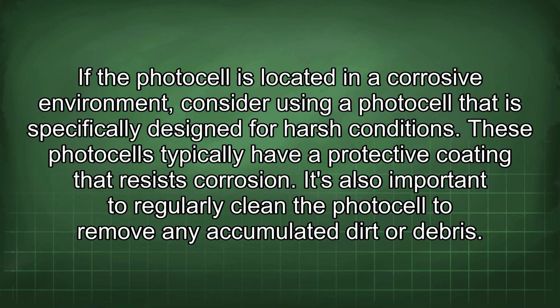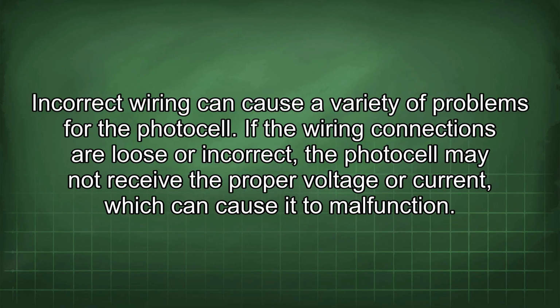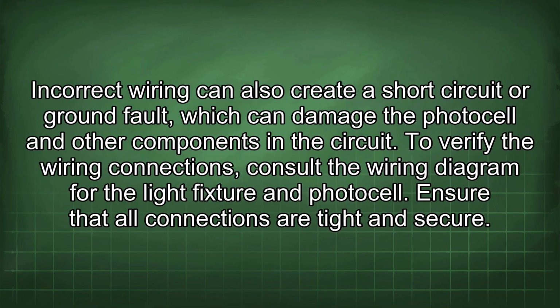It's also important to regularly clean the photocell to remove any accumulated dirt or debris. Incorrect wiring can cause a variety of problems for the photocell. If the wiring connections are loose or incorrect, the photocell may not receive the proper voltage or current, which can cause it to malfunction. Incorrect wiring can also create a short circuit or ground fault, which can damage the photocell and other components in the circuit.